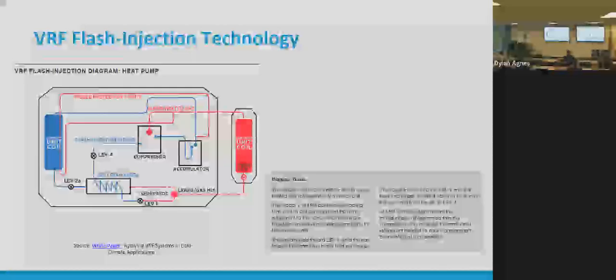So anyways, the way they solve this cold weather performance in variable speed is to say, well, we just got to cool it down, right? Obvious, easy answer. So some VRF manufacturers, and I don't think mini splits do flash injection that I know of, but they steal a little bit of cool liquid and send it back to the compressor to cool it down. Others have a separate refrigerant circuit that gets activated to cool the compressor down. But this stuff is pretty common in industrial compressor applications too. So anyways, really cool. This is what allows those heat pumps to keep sucking heat out at -30.